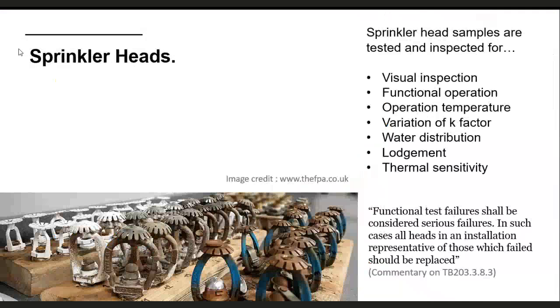So the sprinkler heads themselves, I know that the FPA, the Fire Protection Association, offer this kind of sprinkler head testing and examination. I imagine they're not the only place that will do it, but that's an example of somewhere you can send your sample sprinkler heads. They will do a visual inspection. They'll check the function of the sprinkler head, so they'll set them off at 0.35 bar under the appropriate heat. They'll check: do they operate at the correct temperature? Do they discharge the water in the way they were designed to?